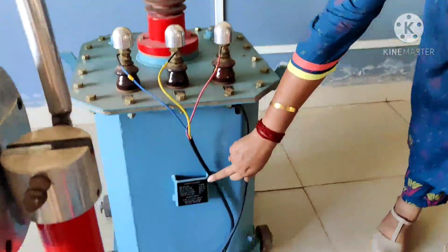Now that 230 volt AC which is coming goes to this transformer. This is a high voltage transformer, and you can check the ratings: KVA rating is 2.5 kVA, input voltage is 220 volt AC, output voltage is 50 kilovolt AC, current is 50 milliamperes, and the type of cooling is oil.